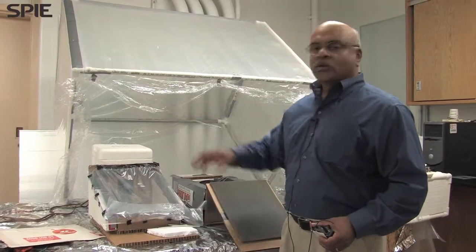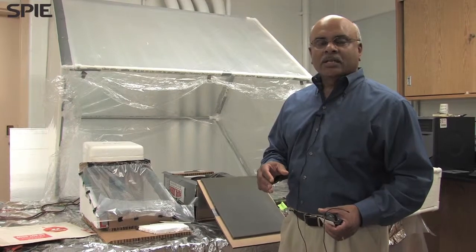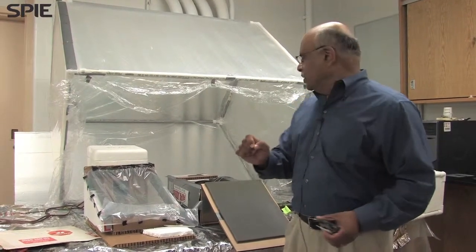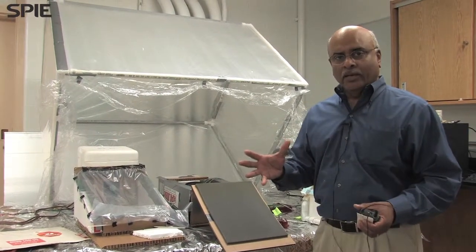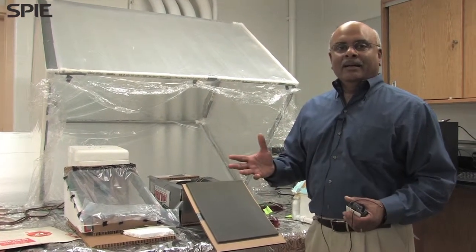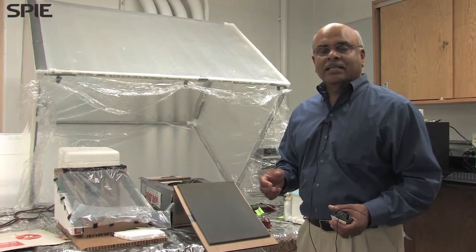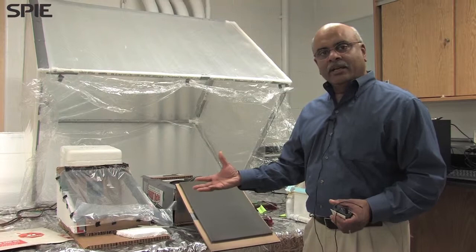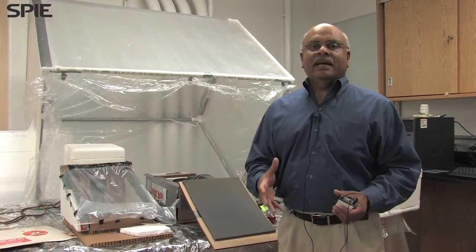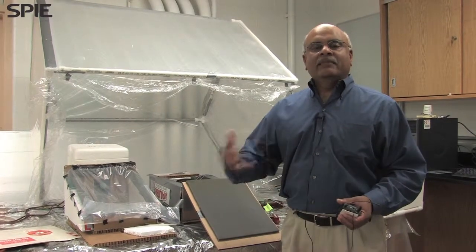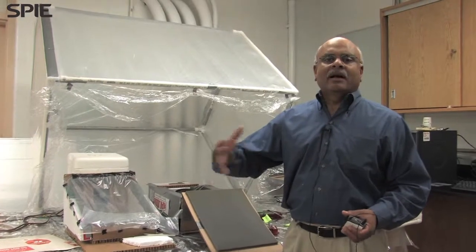And the temperature control piece of it will be a chamber that can be reused and built with low cost components with yet another innovation, the use of a simple clay pot for evaporative cooling. And in many hotter regions of the world, shade temperatures can reach 42 degrees Celsius. And you want to keep the incubator at a comfortable 37 degrees. And the only way to achieve that is to actually cool the chamber. And so this innovation is also going to be added to that.